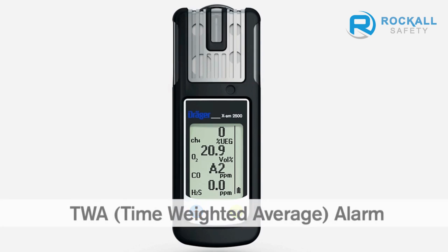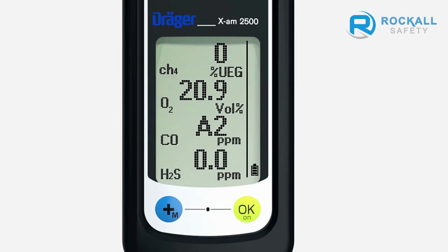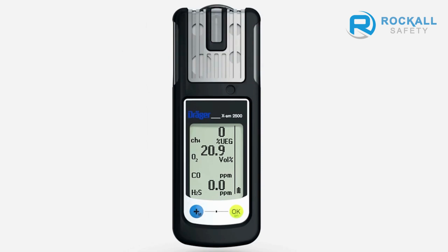In a TWA alarm, audible, visual, and vibration alarms are also periodically repeated. The TWA symbol flashes in the display on the right. A2 alternates with the gas concentration. You must leave the danger zone immediately. The A2 alarm cannot be acknowledged. The TWA and STEL values are deleted as soon as the device is reset.